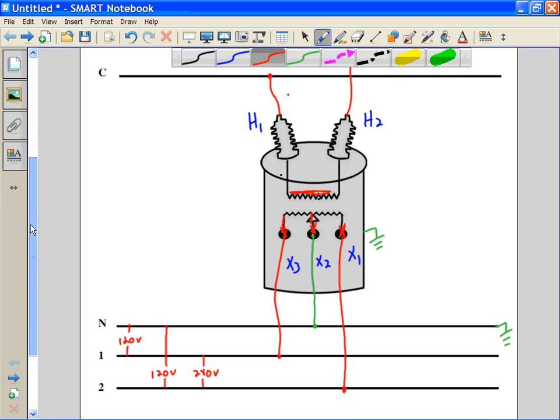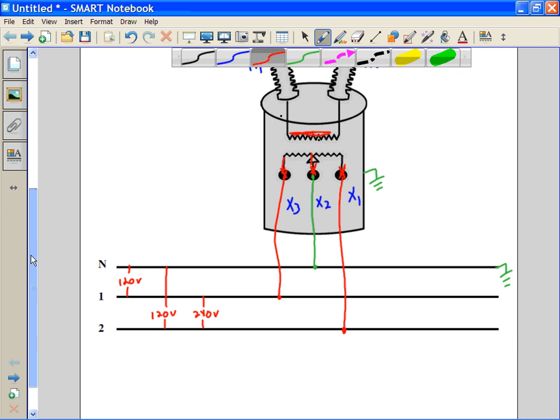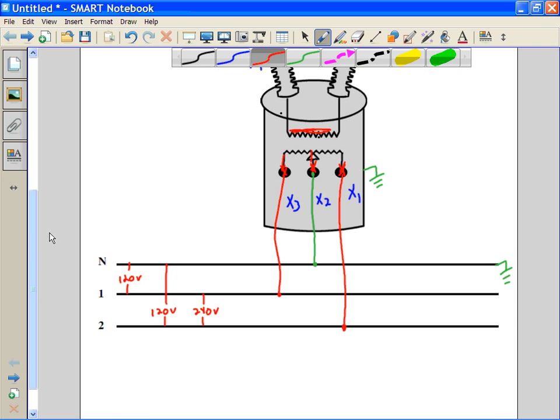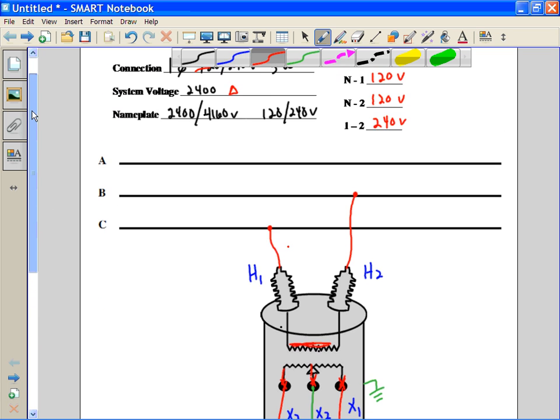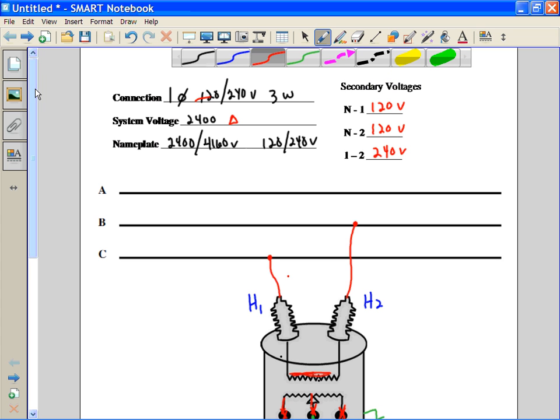Nothing else changes. The secondary will be connected exactly the same way. The transformer tank is grounded, neutrals are grounded. It's just that in this case we have a delta system instead of a Y system that we're connecting to.